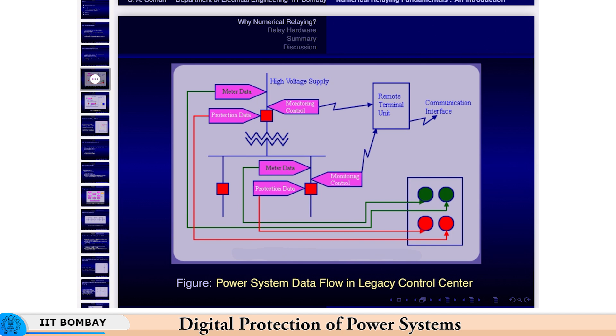Now, one thing to remember here is that since there is no common time reference available, you cannot really use phasor data. So in SCADA you generally use real power and reactive power, which are not phasor quantities, they are scalars. So there is no angle information; it's masked because you use VI star. So you use quantities like voltage magnitude, real power, reactive power, etc. for your other computations.